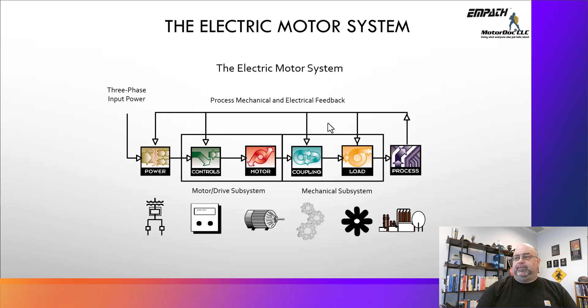Now, what is electrical signature analysis? This is part of the difference between the Empower and the Empath. The Empath is a pure electrical signature analyzer, 3 phases of voltage, 3 phases of current. By definition, it's a power analyzer. So I'm looking at voltages upstream, current is downstream, and then I've got all the power quality in between.